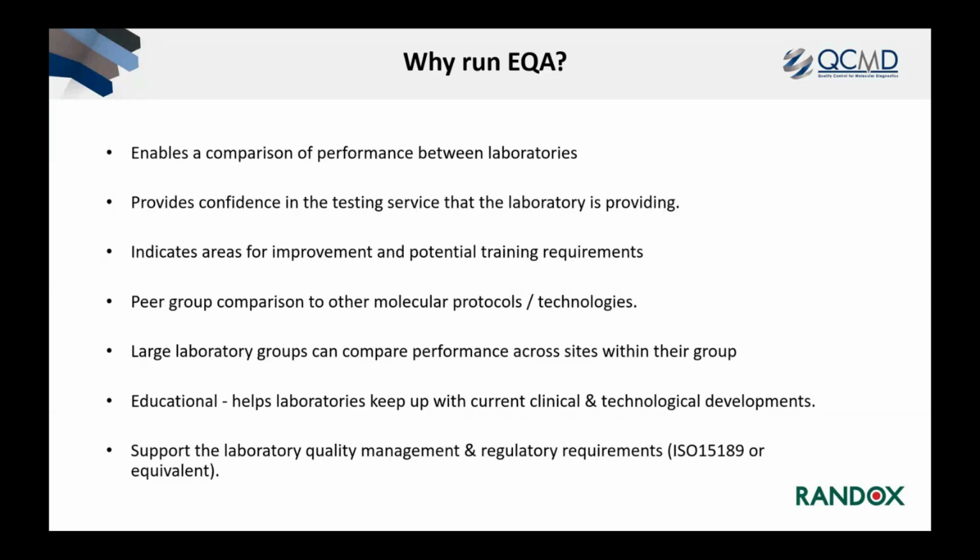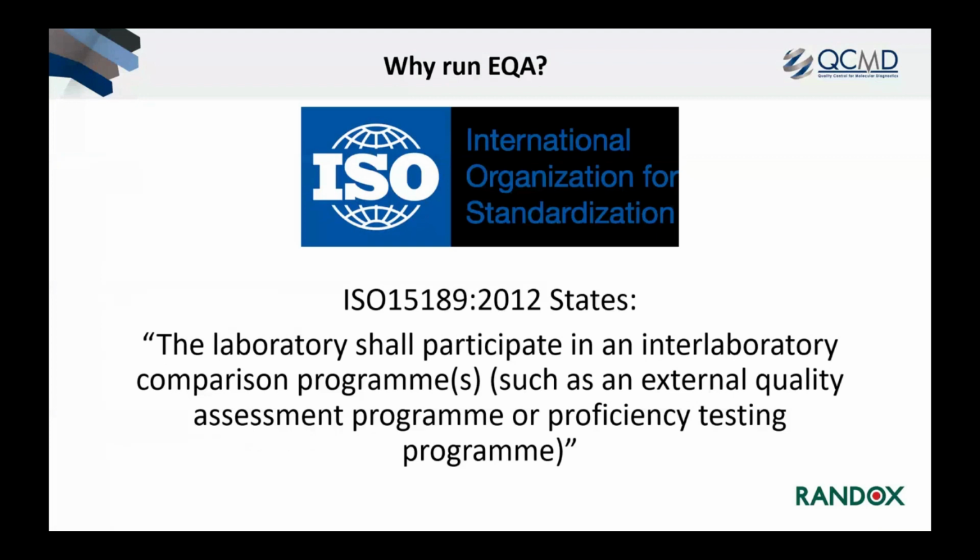It's educational, so it allows laboratories and users to keep up to date with current clinical and technological developments, new analyzers, new assays that are coming on the market. And importantly, it allows laboratories to meet quality management regulations such as ISO 15189:2012 or equivalent. It actually states within ISO 15189:2012 that EQA is mandatory. So ISO 15189:2012 states that the laboratory shall participate in an inter-laboratory comparison program such as an EQA or proficiency testing program.